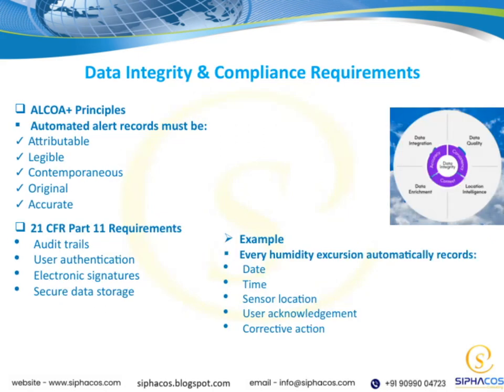When it comes to data integrity and compliance, every detail counts. For example, anytime humidity goes outside the set range, the system automatically logs the date, time, sensor location, who acknowledged it, and what corrective action was taken. This follows the ALCOA plus principles, meaning records must be attributable, legible, contemporaneous, original, and accurate. On top of that, regulations like 21 CFR Part 11 require audit trails, user authentication, electronic signatures, and secure data storage to keep everything trustworthy and compliant.